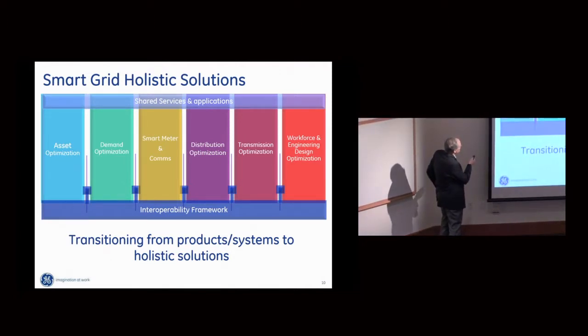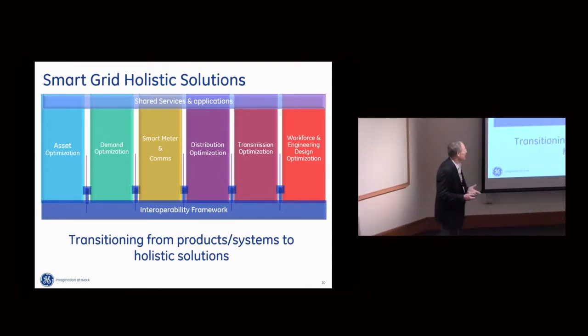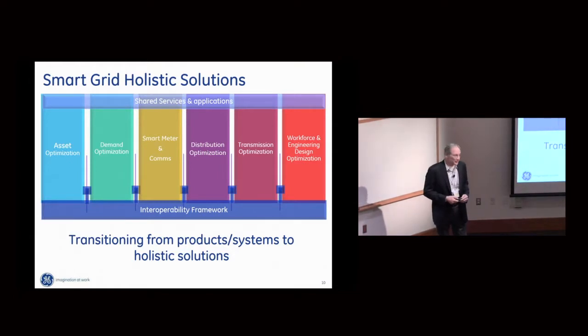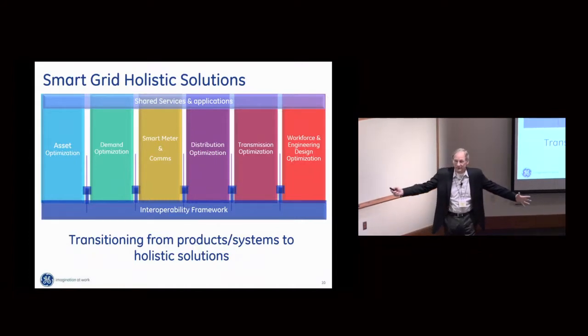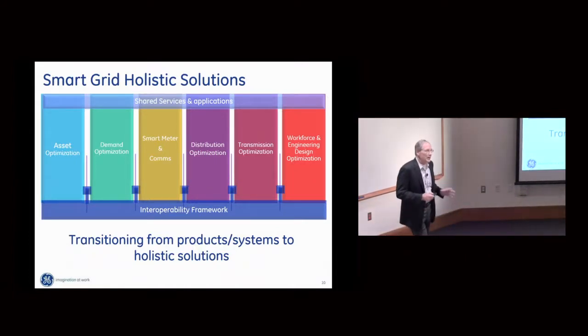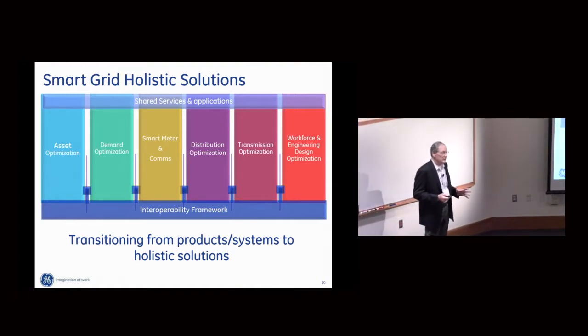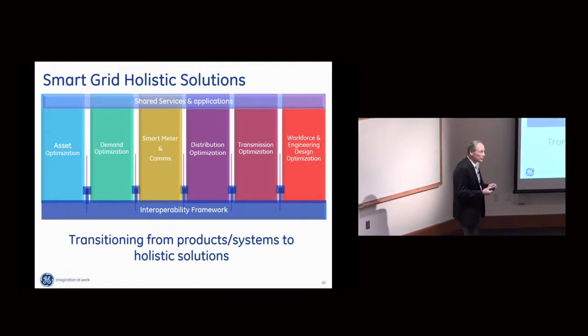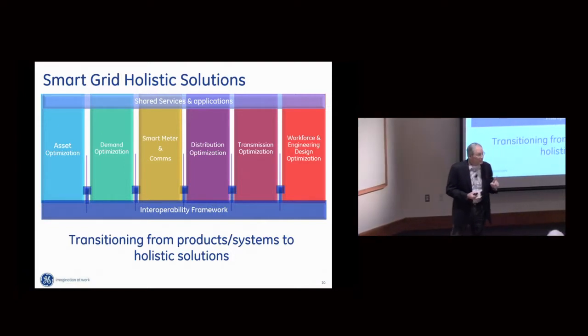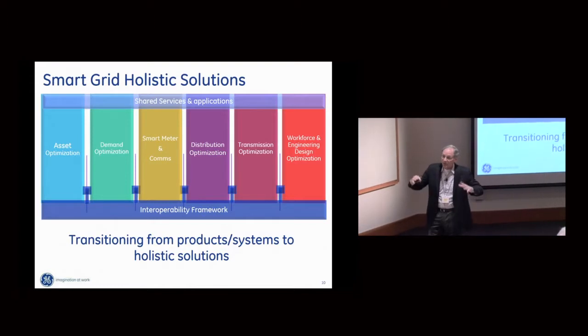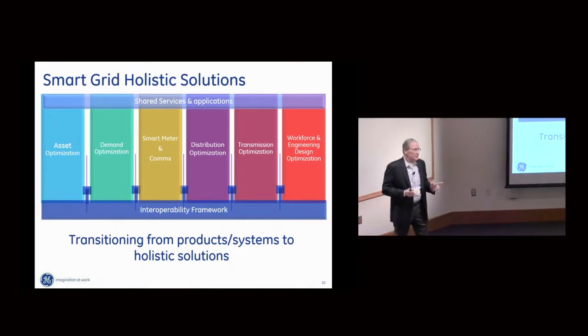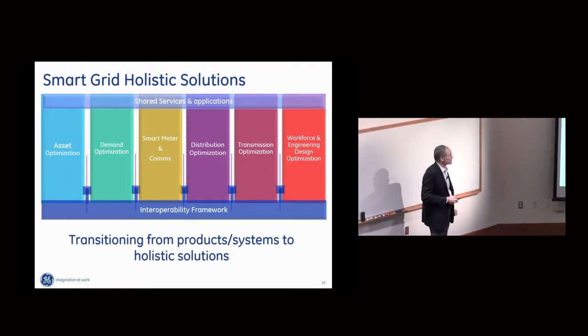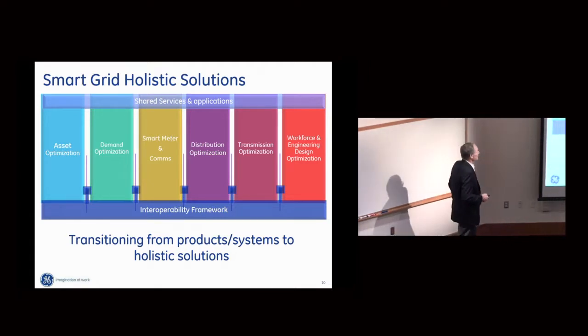Asset optimization—the first step here is transformers. Now we're focused on switchgear, circuit breakers. Third will probably be battery systems. If the battery goes out in the substation, your relaying is inoperative. So battery monitoring systems are key, and there's standardization work going on in the IEEE saying we're not just interested in the voltage of these battery monitoring systems, but a lot of other metrics related to the health of that integrated system. There's standardization work going on by a group in the IEEE PES in terms of what metrics we need from a battery monitoring system.